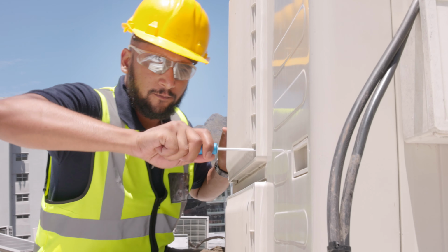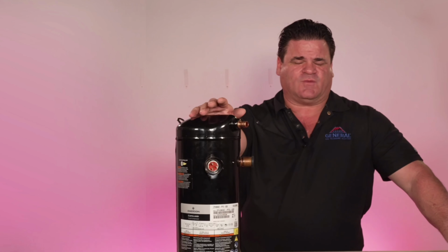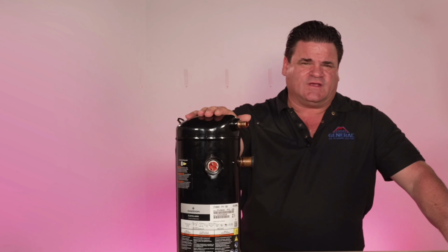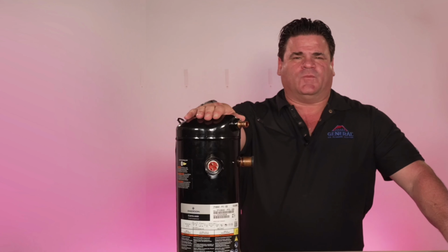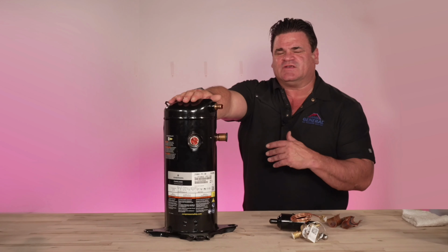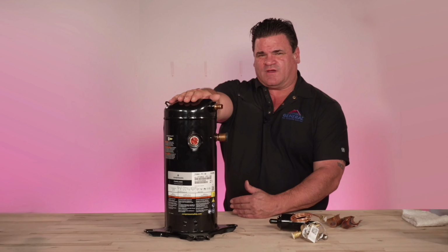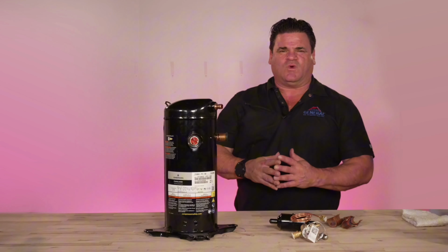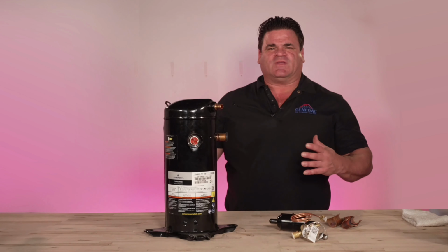And it had to do with the condenser fan motor. It was a two-stage condenser fan motor, had a low and a high, but that was the issue that took out the compressor. So we were able to get the system fixed. It's under warranty. Now, though, a good technician is going to say, why did the condenser fan motor have issues? Is it simply a mechanical piece of equipment that had its issues, or is there something else causing it?